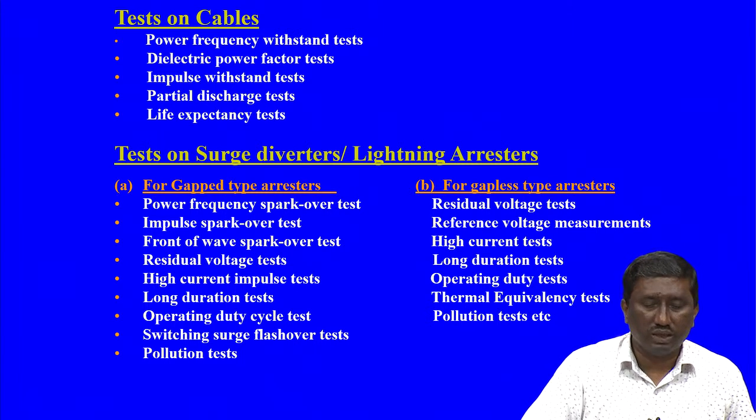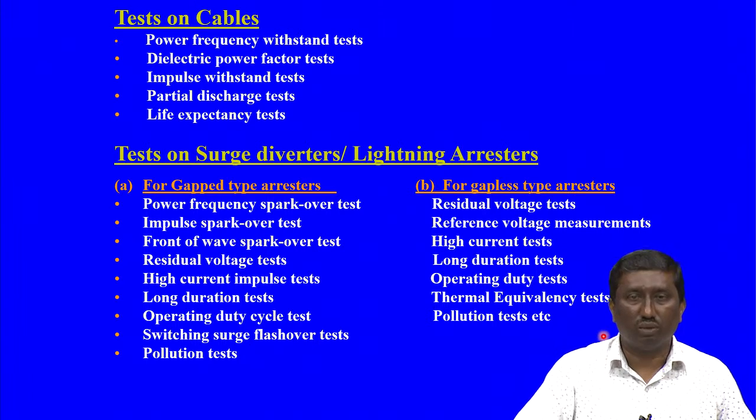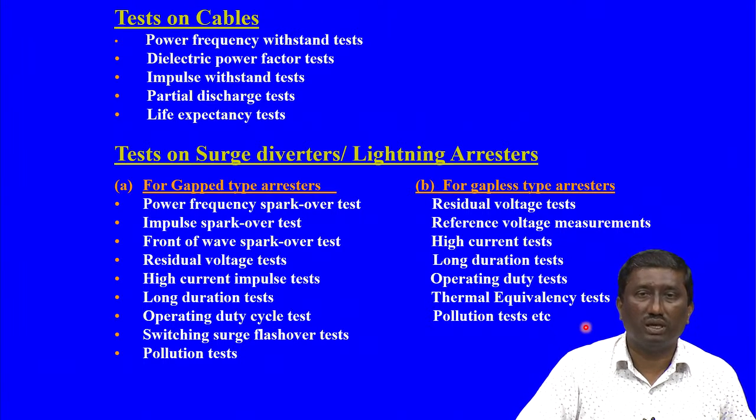Then life expectancy, that is, how long the cable could be in service. So, there are again prescribed tests to estimate the life expectancy for the service. A suitable voltage and time with an acceleration factor is normally applied in the laboratories, and the life expectancy measurements are carried out.